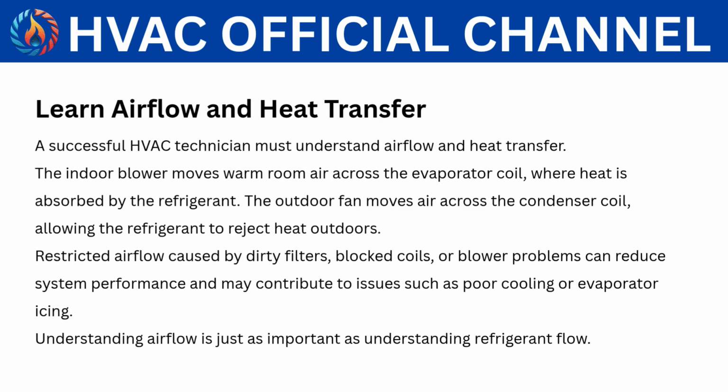Learn airflow and heat transfer. A successful HVAC technician must understand airflow and heat transfer. The indoor blower moves warm room air across the evaporator coil, where heat is absorbed by the refrigerant. The outdoor fan moves air across the condenser coil, allowing the refrigerant to reject heat outdoors. Restricted airflow caused by dirty filters, blocked coils, or blower problems can reduce system performance and may contribute to issues such as poor cooling or evaporator icing. Understanding airflow is just as important as understanding refrigerant flow.